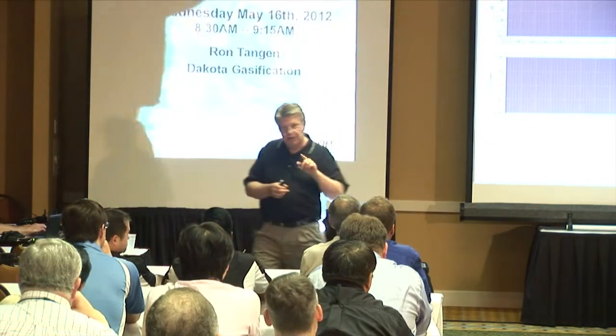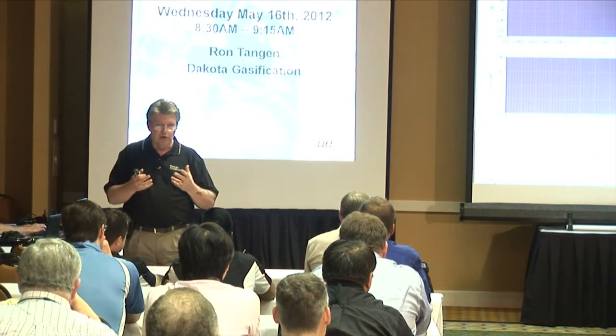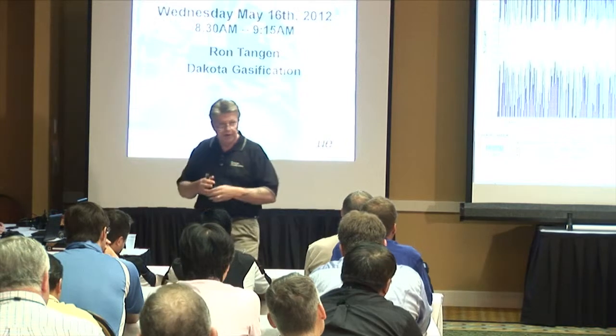This last example is spalling. You will hear that there is a cyclical nature to it, but it's a lot more gravelly and rough-sounding. You can see there's a lot more energy in the baseline on a spalling condition.